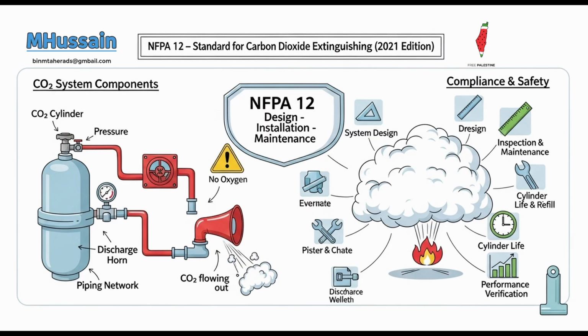What about ongoing checks? Then there's ongoing care. Inspections must be conducted at least every 30 days. Monthly checks. A quick visual check to assess operational condition. This includes verifying that all cylinders are in place and secured, checking normal pressure and valve status for low-pressure units, ensuring the CO2 storage is properly connected, that manual actuators and tamper seals are intact, nozzles are clear of obstructions, detectors are in place, and the control panel shows a normal ready condition. Quick visual look over each month. This regular visual check can catch minor issues before they become major problems.